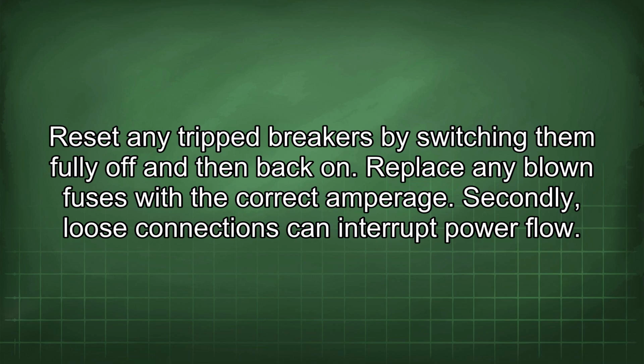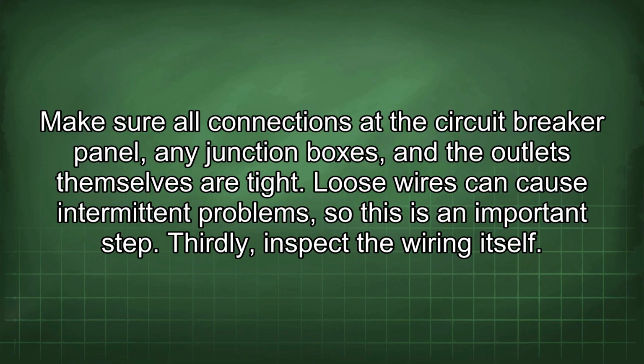Secondly, loose connections can interrupt power flow. Make sure all connections at the circuit breaker panel, any junction boxes, and the outlets themselves are tight. Loose wires can cause intermittent problems, so this is an important step.